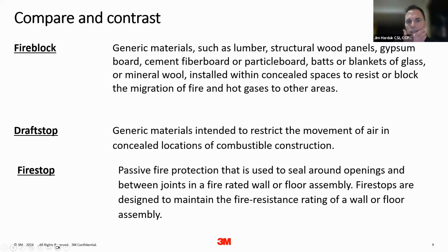And then last but not least, Firestop. Firestop is the passive fire protection that is used to seal round openings in between joints in fire-rated wall and floor assemblies. These are designed to maintain the fire resistance rating of the floor or wall assembly for a specified period of time. And I'll talk a little bit more about that in a couple slides here. Next slide, please.